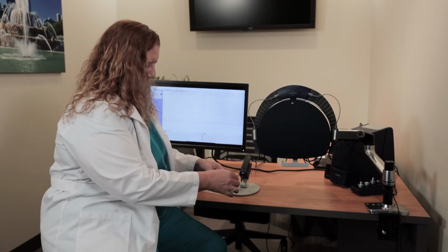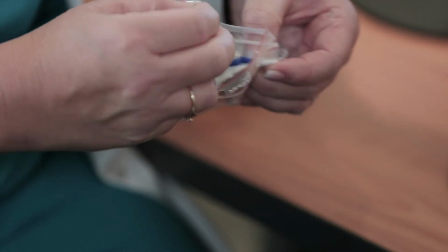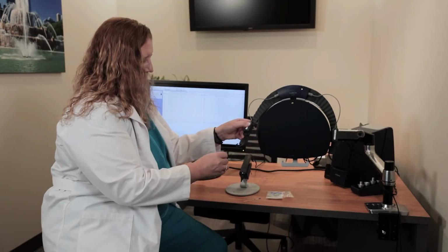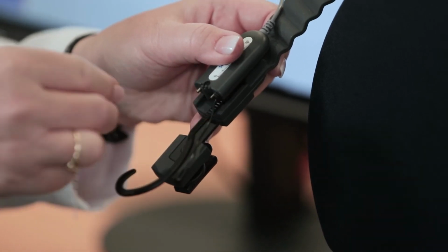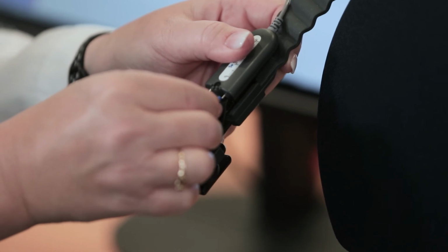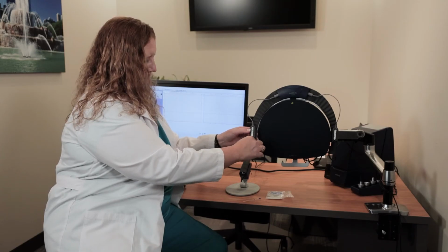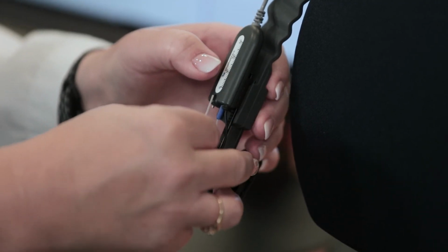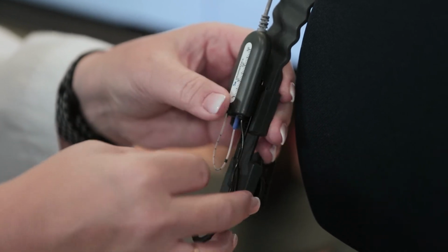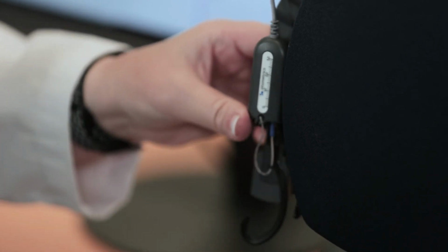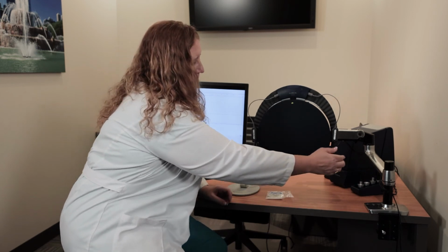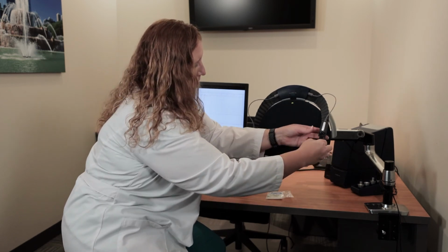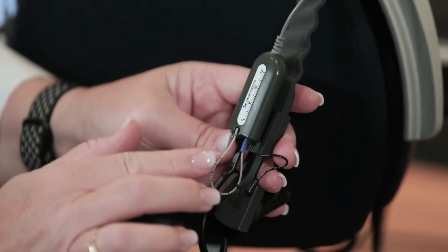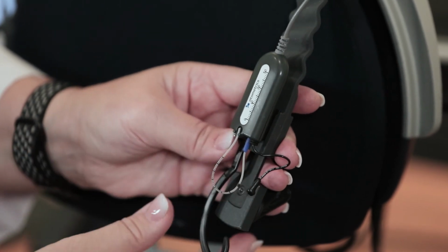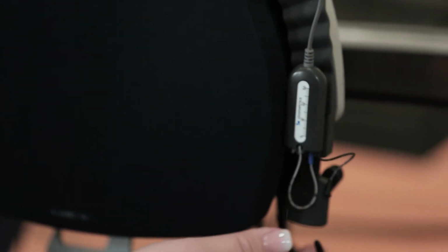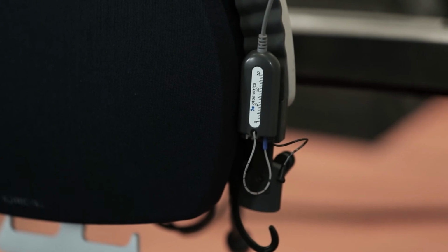Remove the new probe tube or tubes from the package. Connect the probe tubes to the probes and loop the free end of the probe tube upward toward the probe. Slide the tube in between the gray plastic posts near the black circle, which is the reference microphone. Carefully position the end of the probe tube over the reference microphone. Make certain the slanted edge of the probe tube is facing downward over the center of the reference microphone.